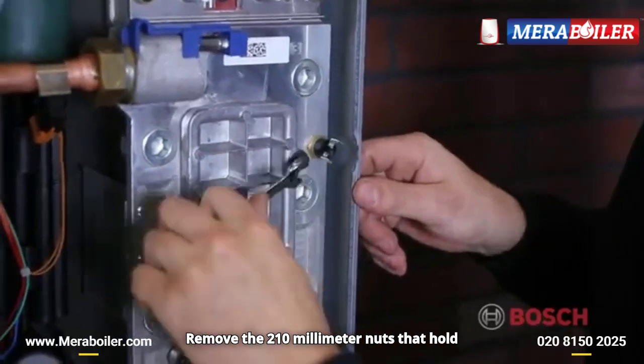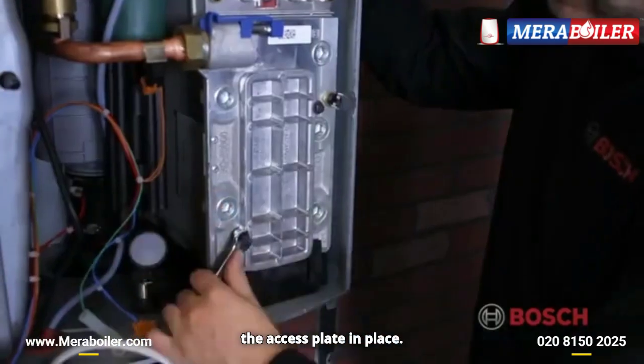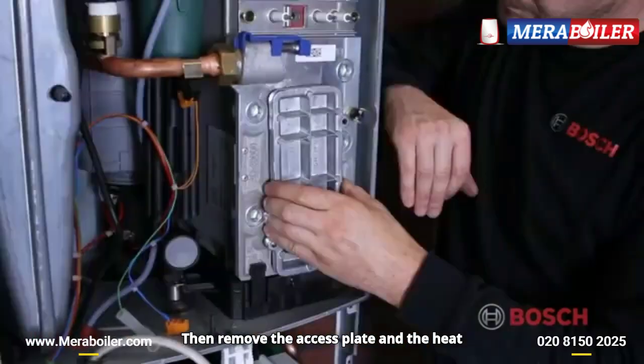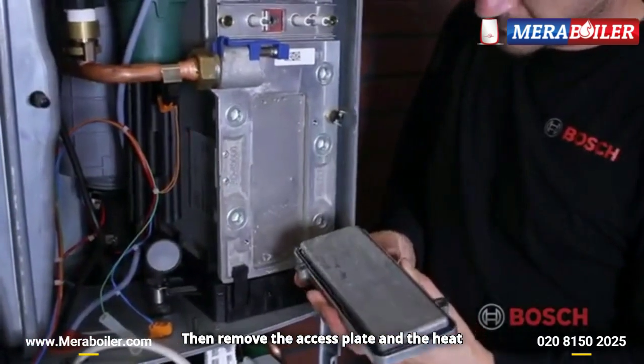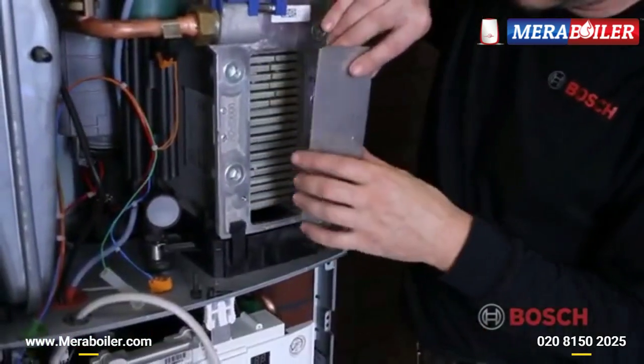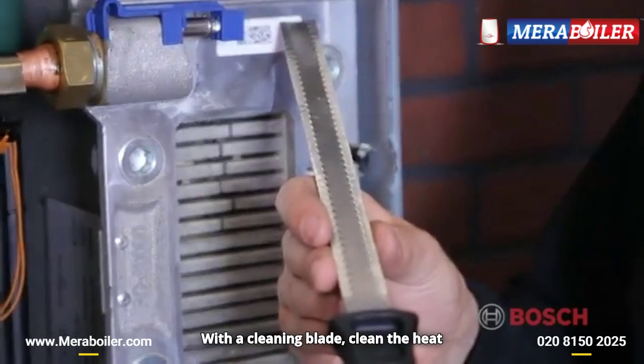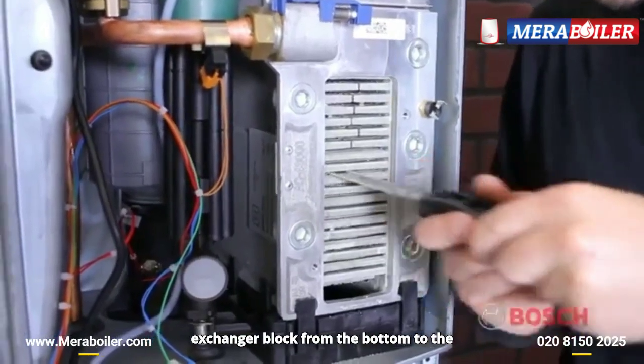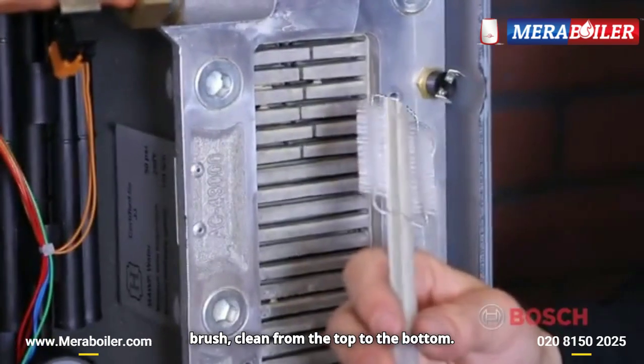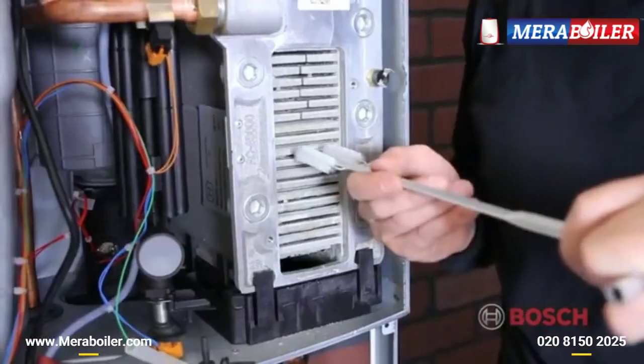Remove the two 10mm nuts that hold the access plate in place. Then remove the access plate and the heat shield. With a cleaning blade, clean the heat exchanger block from the bottom to the top. And then with a brush, clean from the top to the bottom.